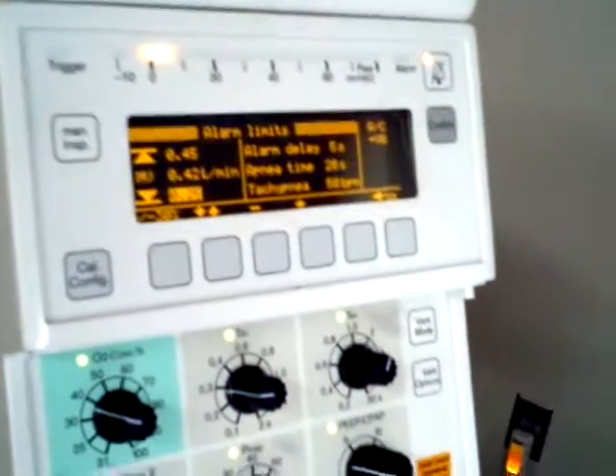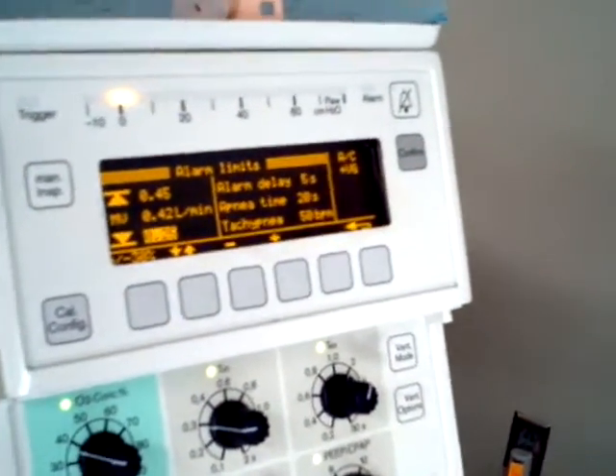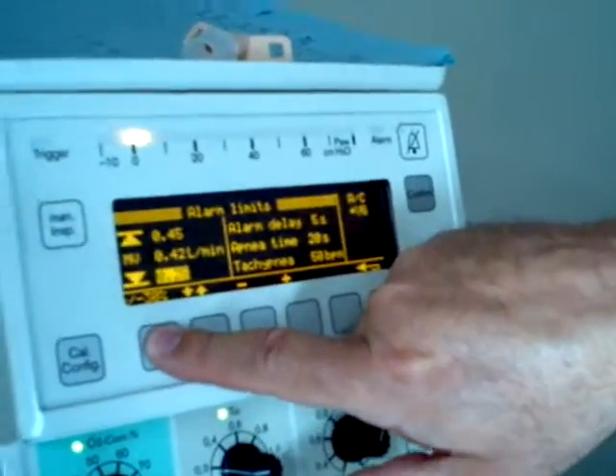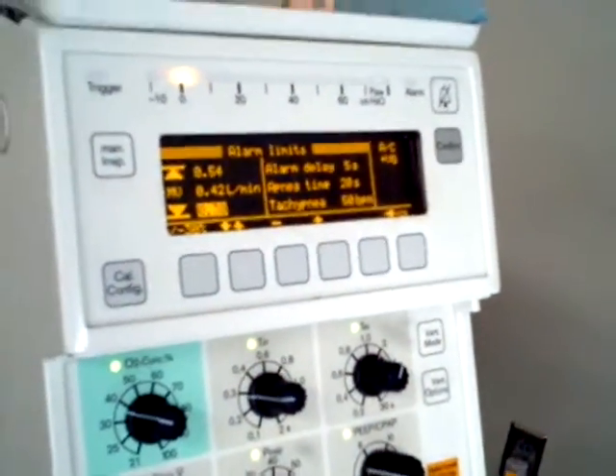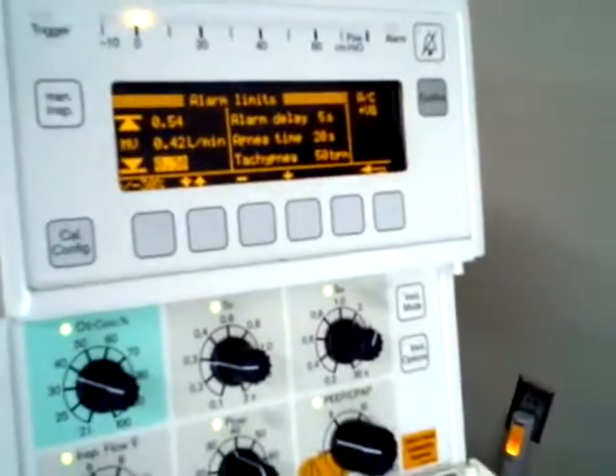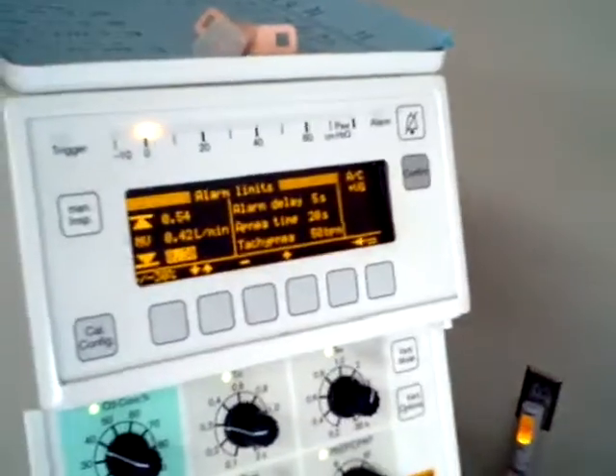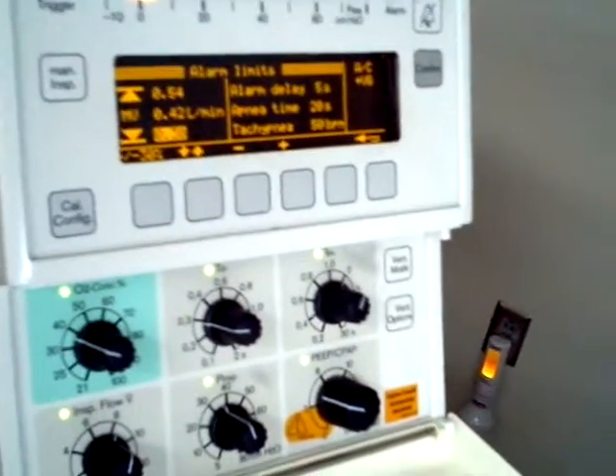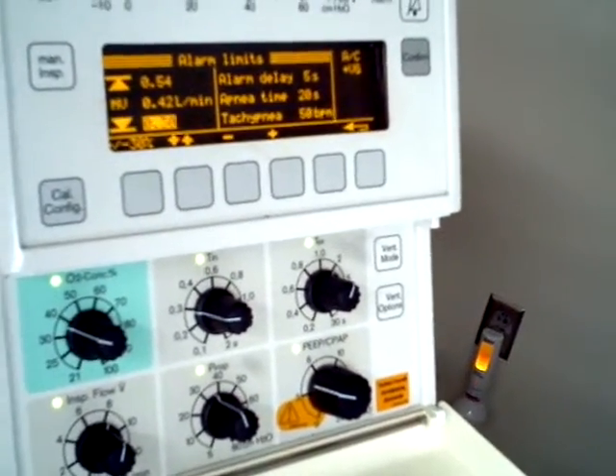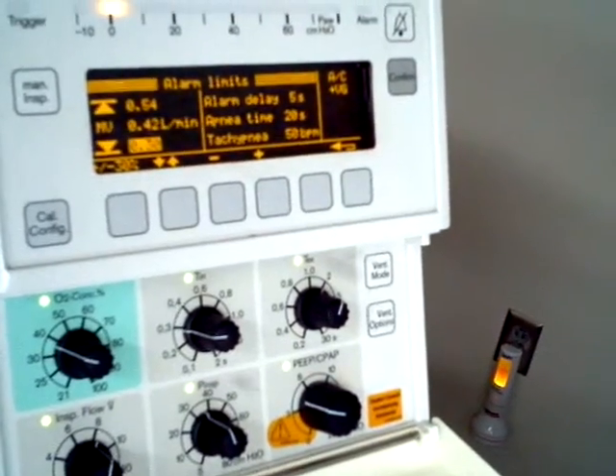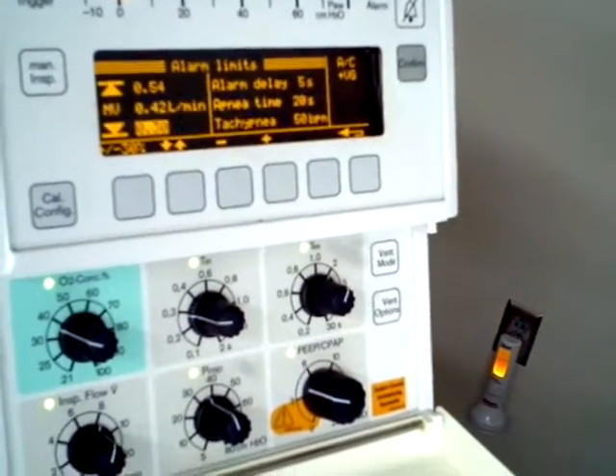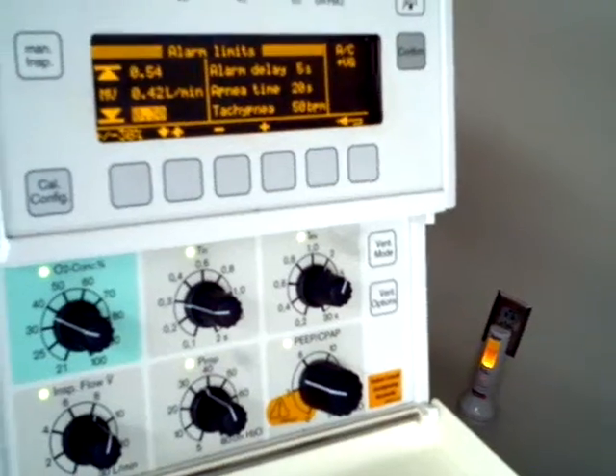Okay, we changed the tidal volume. We changed the minute volume. Notice our alarm settings now. The high one is pretty tight. So let's bring our low one up higher, set our high one up a little bit more, in range of what our current minute volume is. Now in real life, when you're working with the real baby, I want you to think about these ventilator alarm settings a little bit more. But for the most part, I think this is a pretty good range.